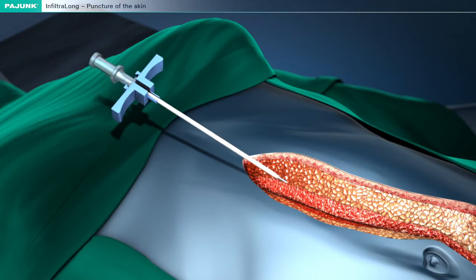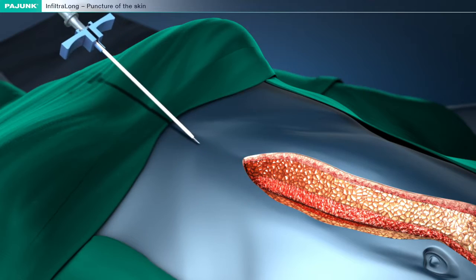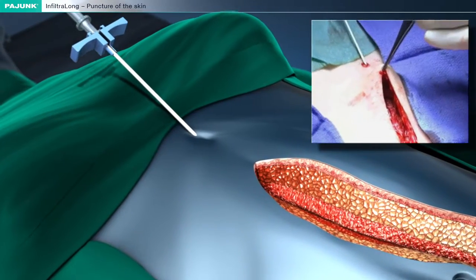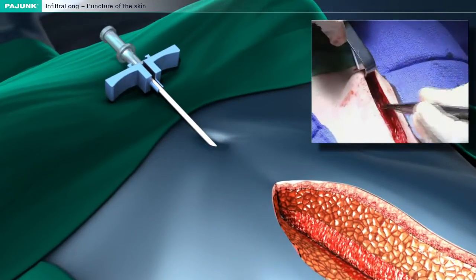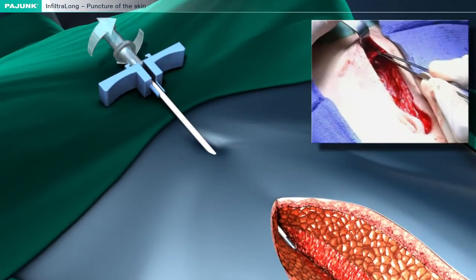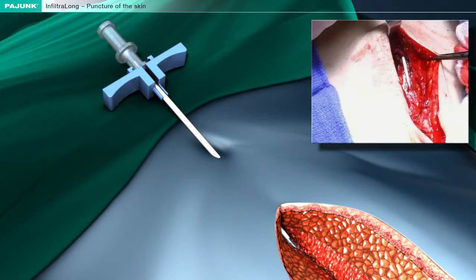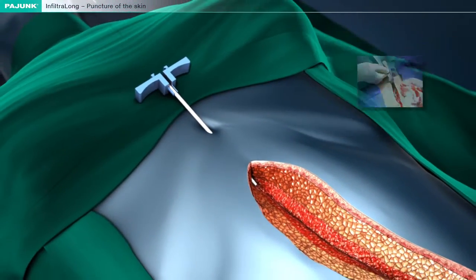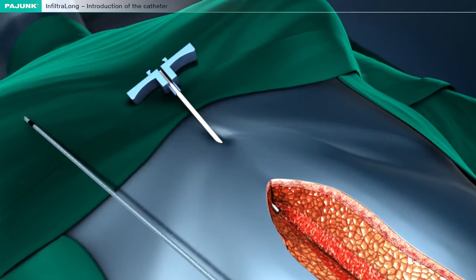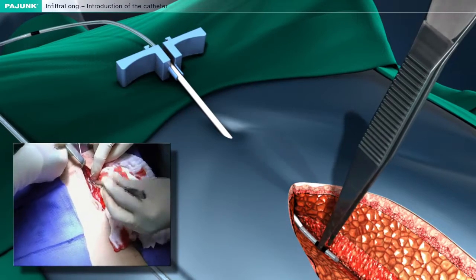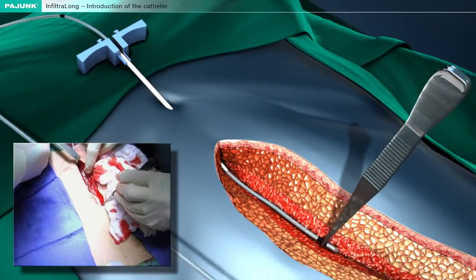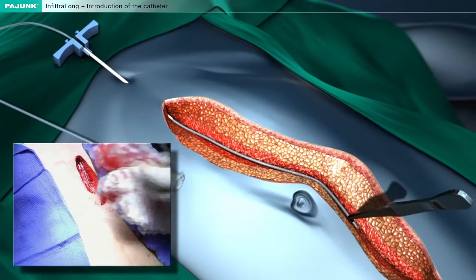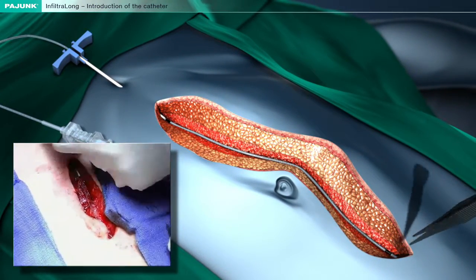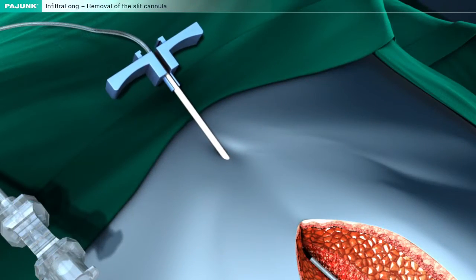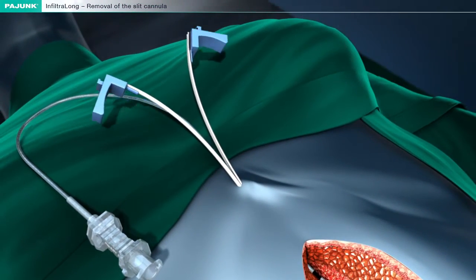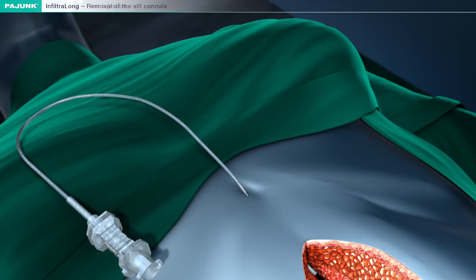The split cannula is introduced through the skin by way of a separate access located within a maximum of 30 to 50 millimeters from the wound to be operated. When the tip is visible in the wound, then the lock can be loosened and the metal cannula is retracted. The catheter is introduced through the split cannula in such a way that the complete perforated segment comes to rest in the wound and the anesthetic will be released evenly. The split cannula is now separated and removed. Then the filter is connected to the catheter.